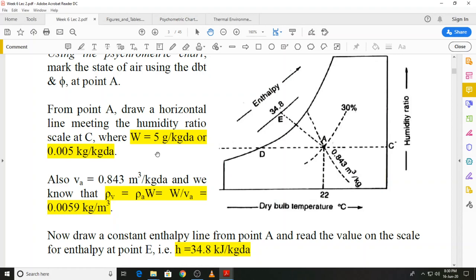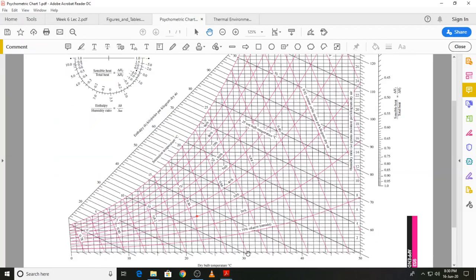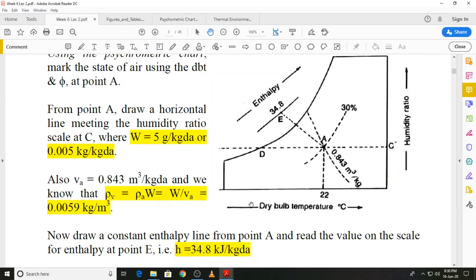To find the humidity ratio, we draw a horizontal line from the state point to the vertical axis and read the value: 5 grams per kilogram dry air. Converting to kilogram per kilogram dry air by dividing by 1000 gives 0.005 kilogram per kilogram dry air.